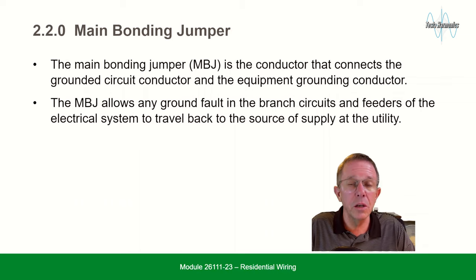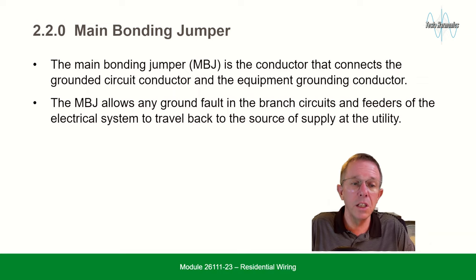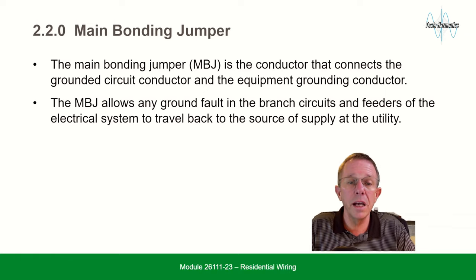Main bonding jumper: the main bonding jumper, or MBJ, is the conductor that connects the grounded circuit conductor and the equipment grounding conductor. The MBJ allows any ground fault in the branch circuits and feeders of the electrical system to travel back to the source of supply at the utility.